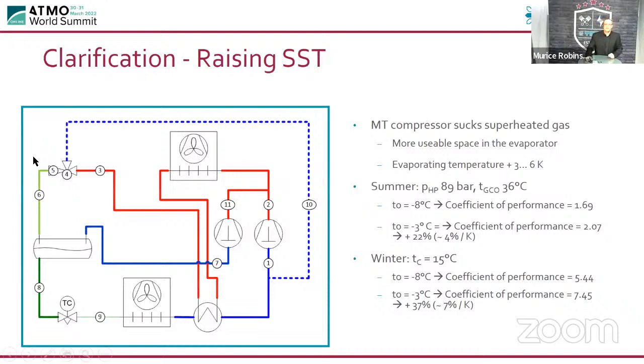So just to clarify raising the suction temperature, just to give you an idea, we all know that the compressor sucks superheated gas. But if we have a look at a summer condition with 89 bar and a gas cooler outlet temperature of 36 degrees, running at -8 gives you a COP of 1.69. If you take those same conditions and run it at -3, you've got a COP of 2.07 already, which means you've got a 22% energy saving straight away just by increasing that suction temperature.